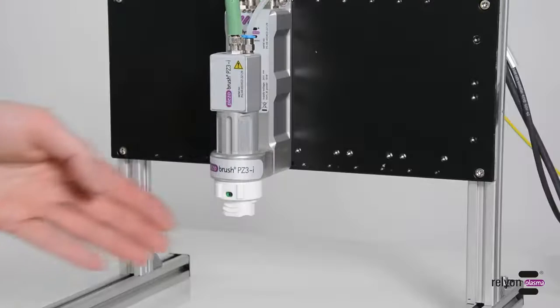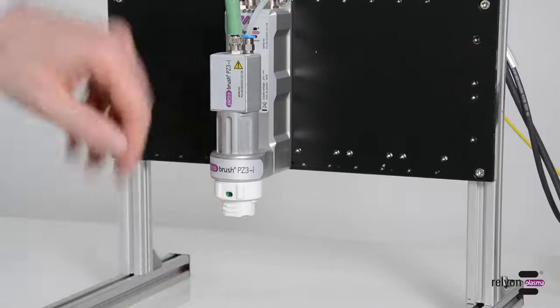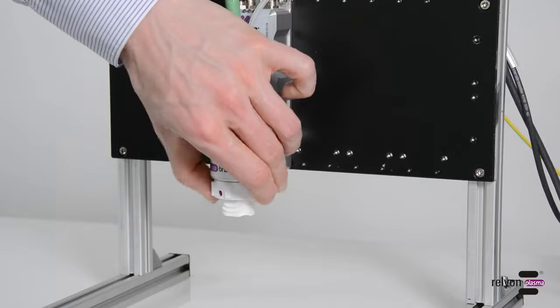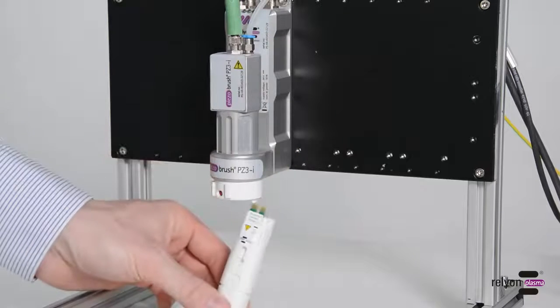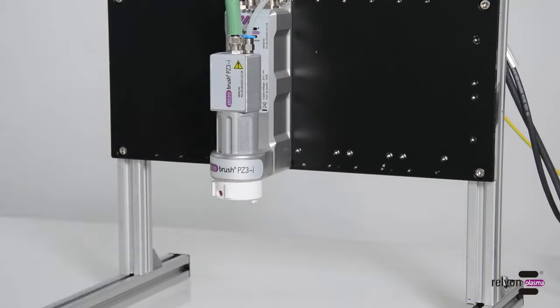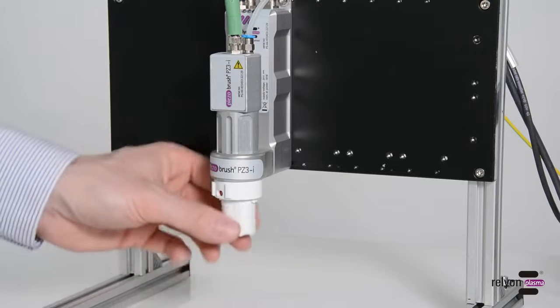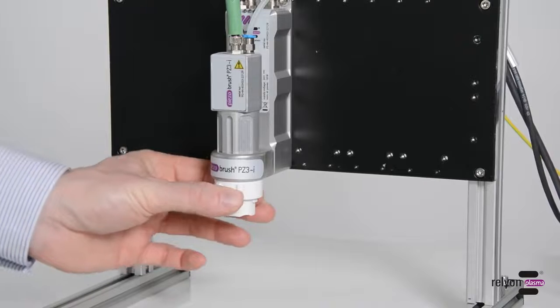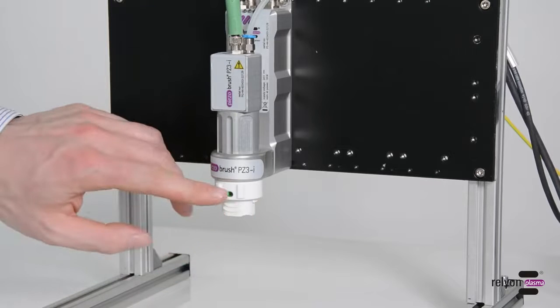If, on the other hand, the device has sufficient free space, the module carrier does not have to be removed. Instead, you can simply loosen the locking ring, remove the module, insert the new module, and close the locking ring.